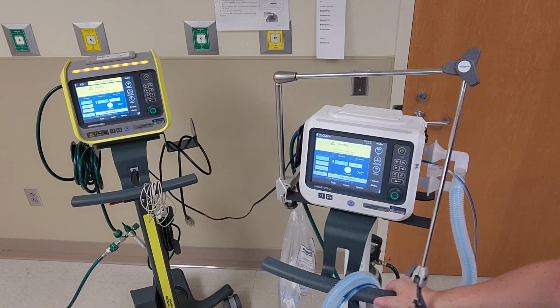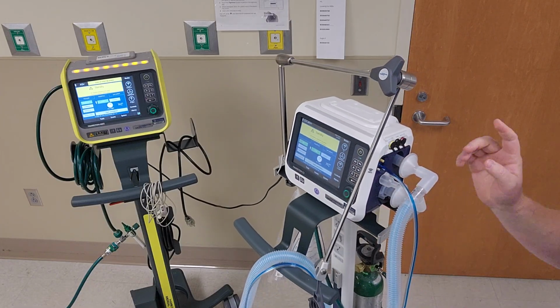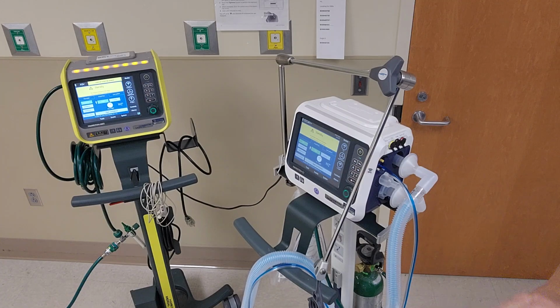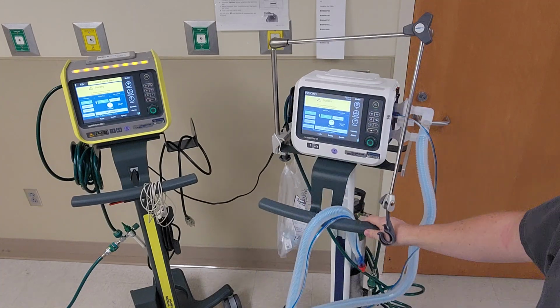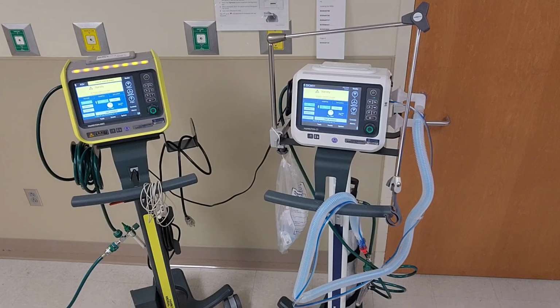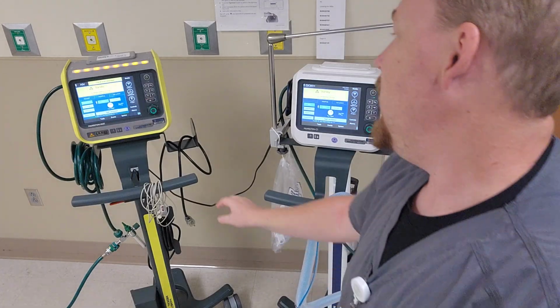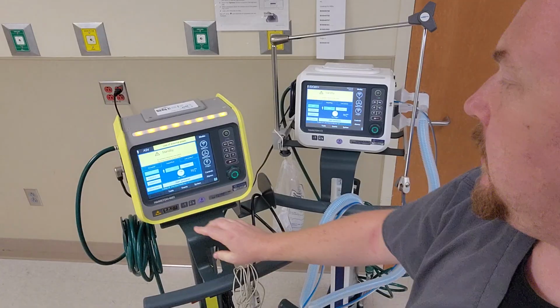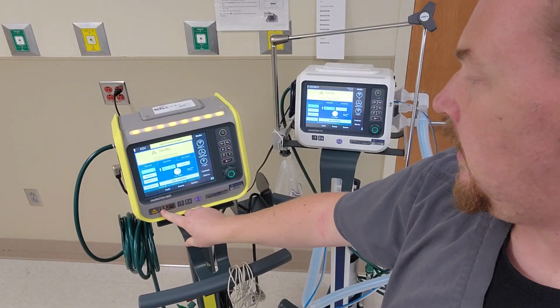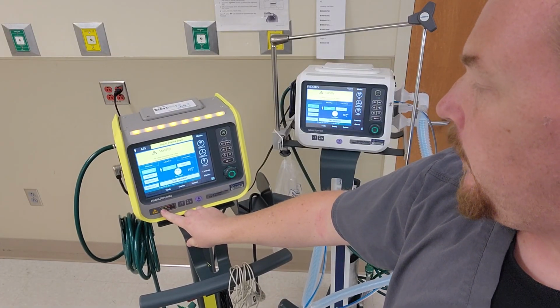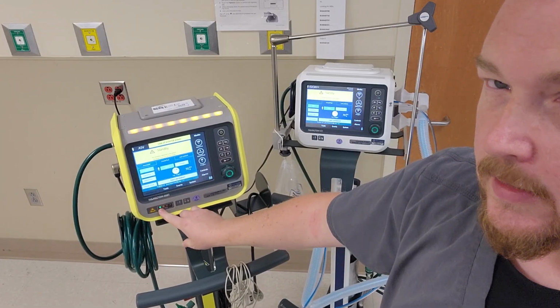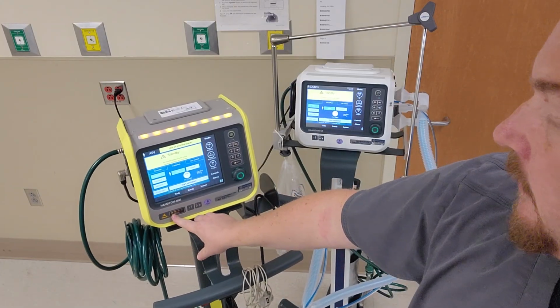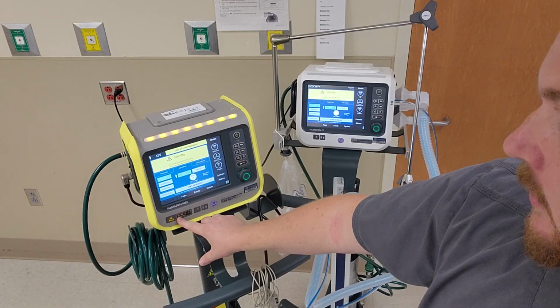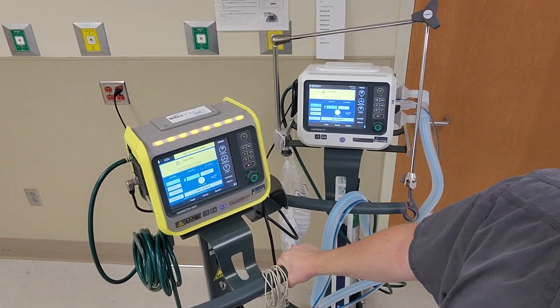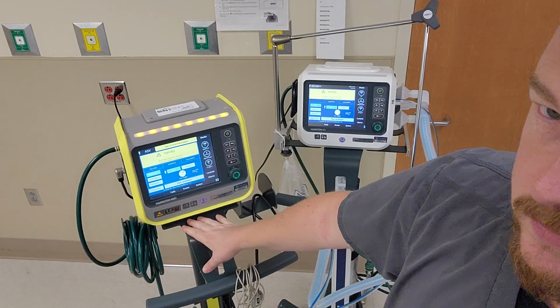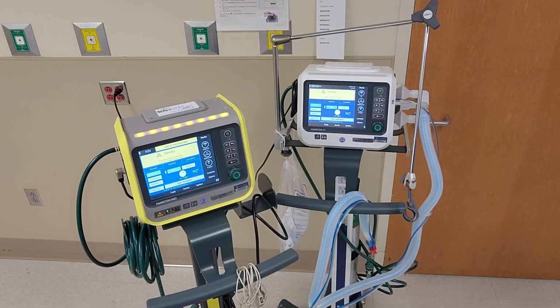Now, these exhalation valves that come in that package are going to be different than the C6 ones. Unfortunately, you cannot mix them up. If you do, well, they physically will not attach. So please don't try. Now, if you look on the front of the MRI vent, there is the Tesla Spy here. It's measuring how many Gauss there are. Before you even bother setting this up, make sure that this little green light here is actually flashing. If it is not flashing, do not even bother setting it up. That means that somebody was not listening to any of the instructions, and they actually got this too close to the device, or to the MRI scanner.